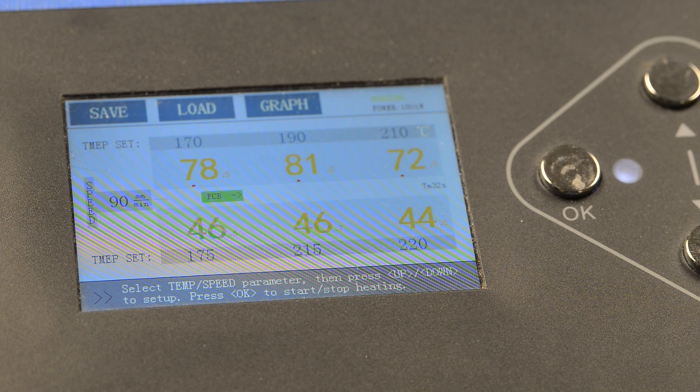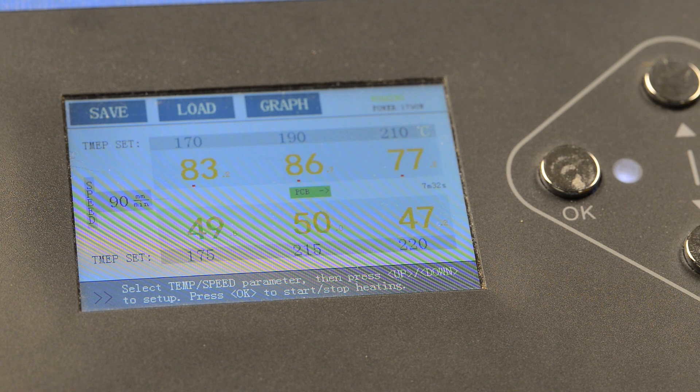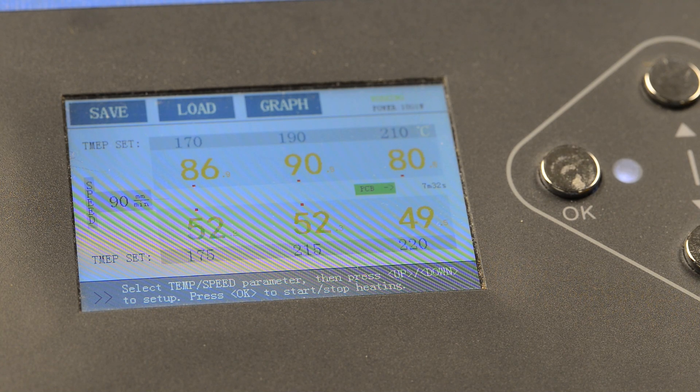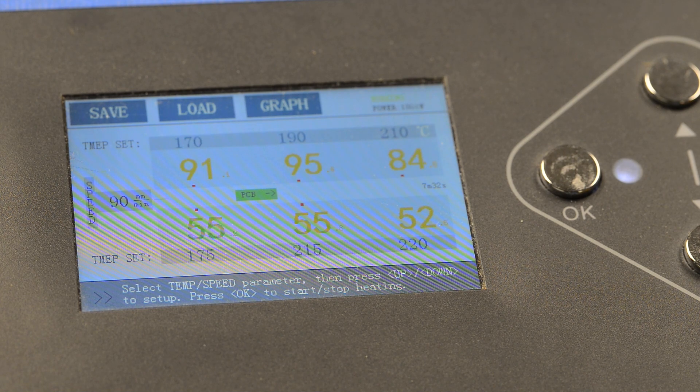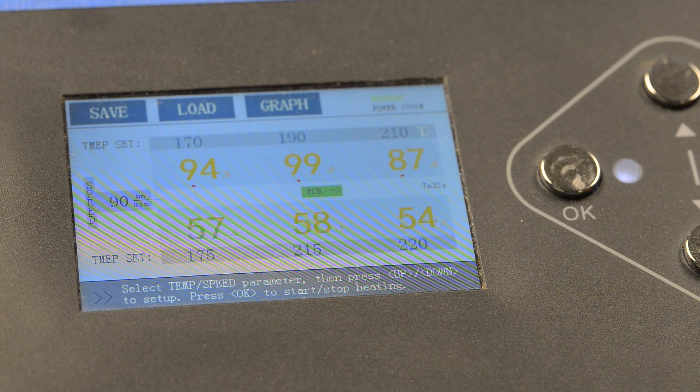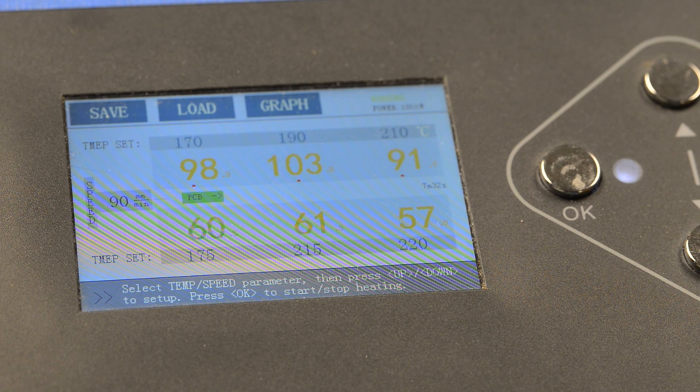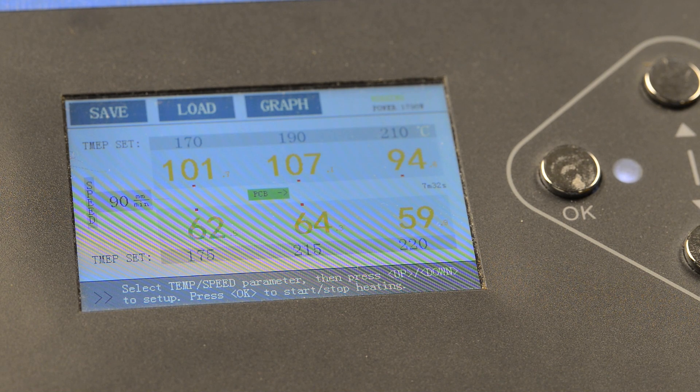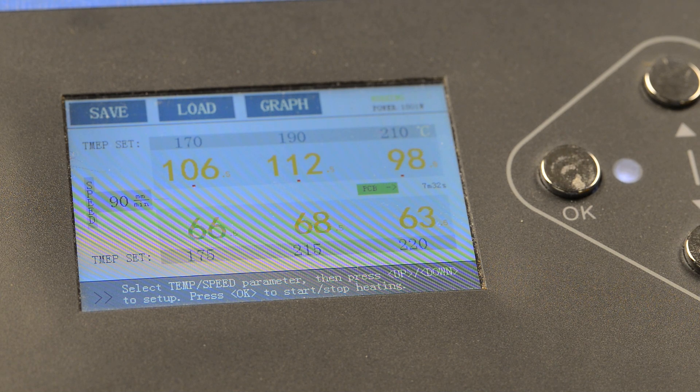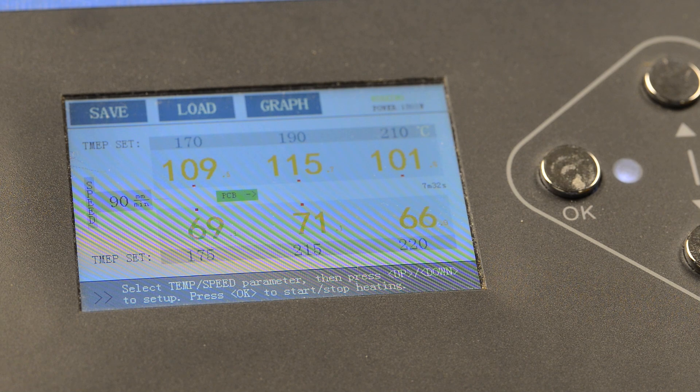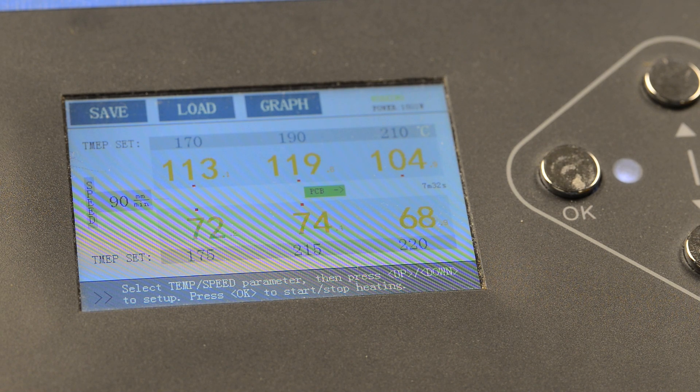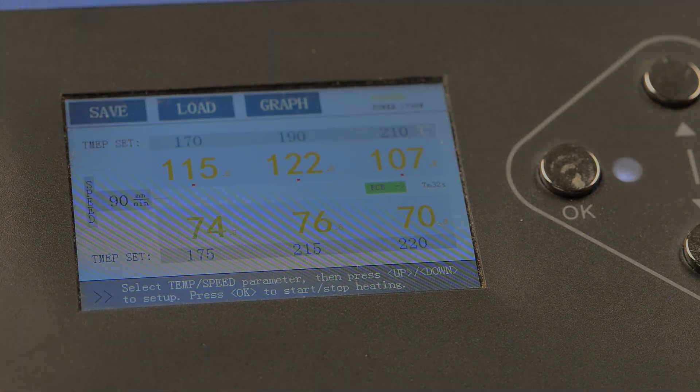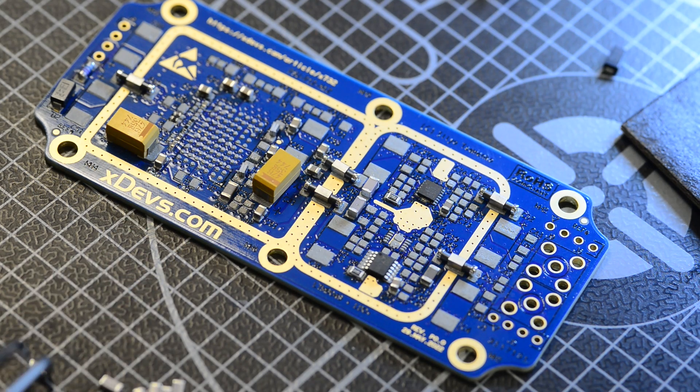This oven has 6 heaters, 3 on the top and 3 on the bottom and each profile setting you can see on the screen. This is actually sped up video so the real time is about 3 times slower than this. And the total conveyor time is 7 minutes 32 seconds with speed 90 millimeters per minute. There are multiple different ways how the board can be heated and reflowed so you can surely find a lot of different tutorials and material online if you just Google SMT reflow oven and SMT reflow process.